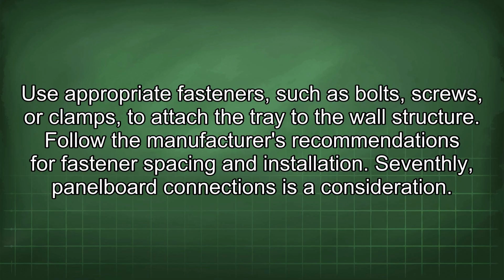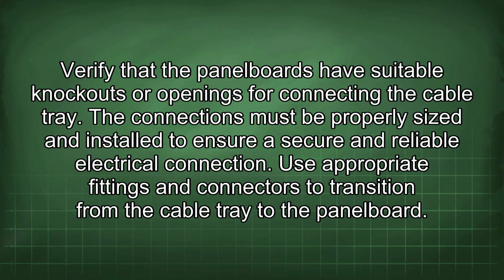Seventhly, panel board connections are a consideration. Verify that the panel boards have suitable knockouts or openings for connecting the cable tray. The connections must be properly sized and installed to ensure a secure and reliable electrical connection.